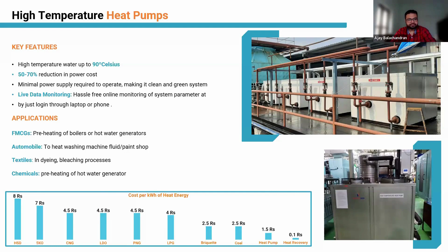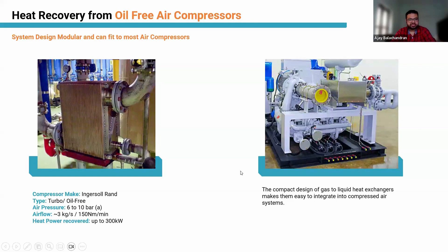Similarly, most industries with oil-free air compressors have a major source of waste heat there. Almost 50% of the energy given into the air compressor, I would say even up to 100% of the energy given into an oil-free air compressor, is being rejected into the atmosphere. Using our system, a minimum of 50% of input energy can be recovered and used again to heat water or any other process liquid in the facility.